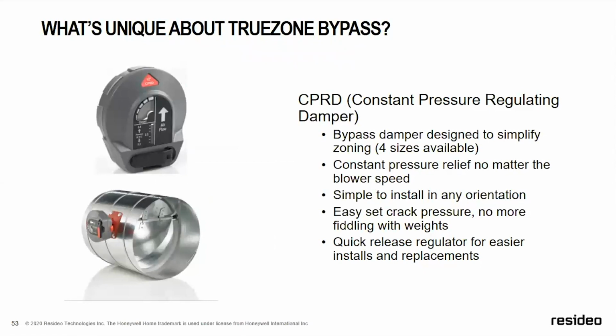The CPRD, the bypass damper, comes in 4 sizes. It is dial set, so easy peasy. You will dial this to the static pressure you need. Typically, it comes set at 0.05, and for 95% of your installations, this is going to be the correct position. You want to call your system with your smallest zone, make sure that your bypass opens. When you call your entire system, let's say you have a 3-zone system, you want to have your bypass closed when all those zones are calling.